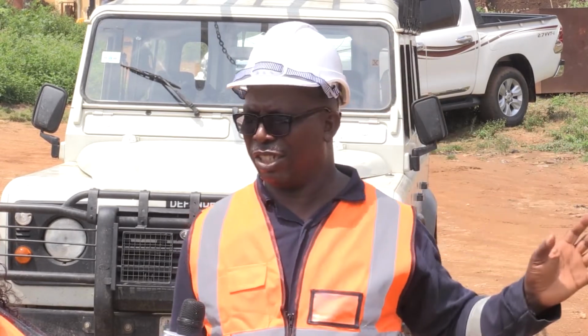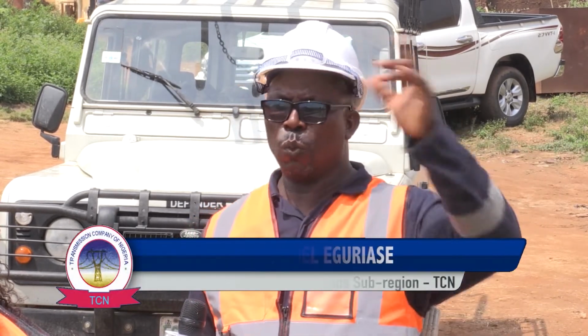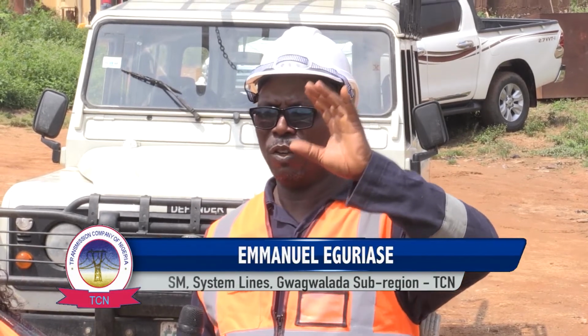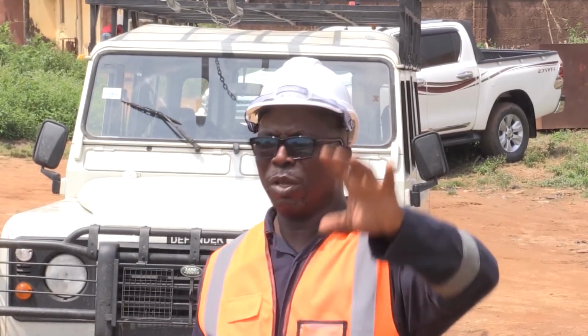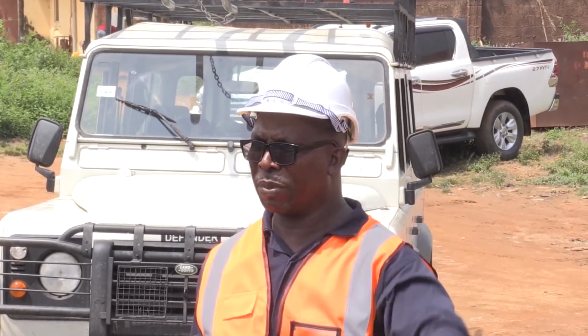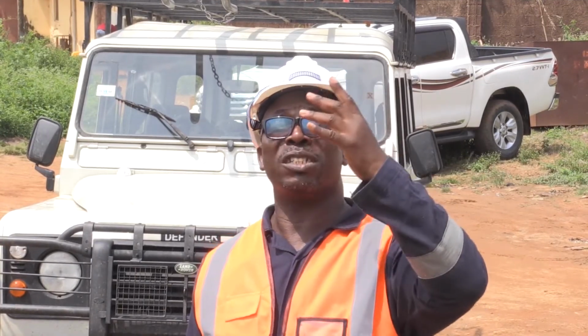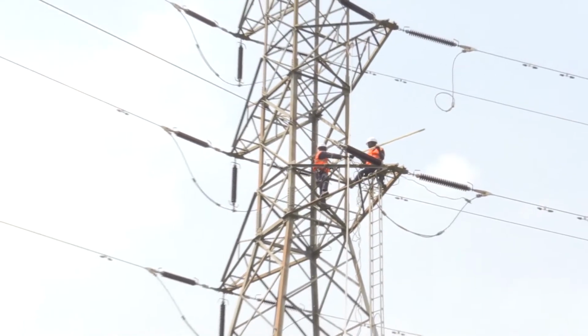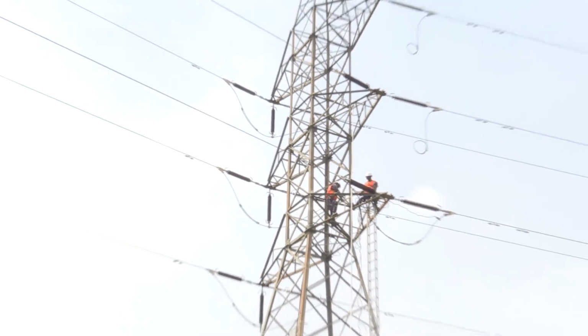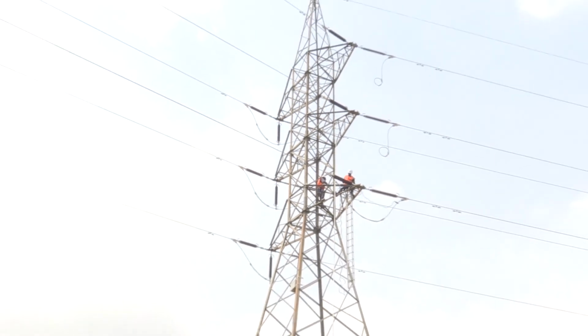After the outage of the line, we are to open jumpers to enable the contractor to do their work at this new substation—that is exactly what we did here. If you look up now, you can see where the jumper was opened, so they have seen physically that the jumper has been opened.